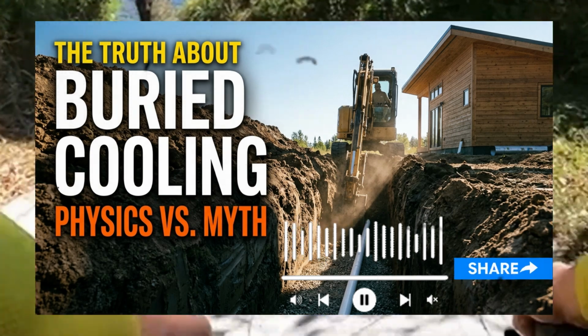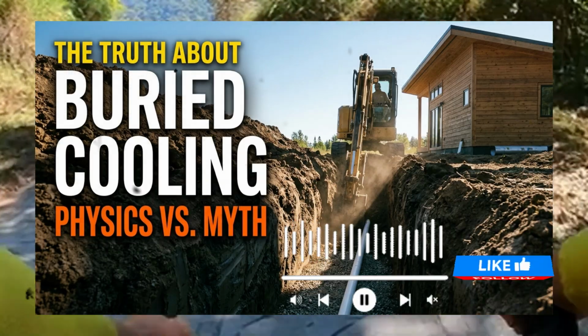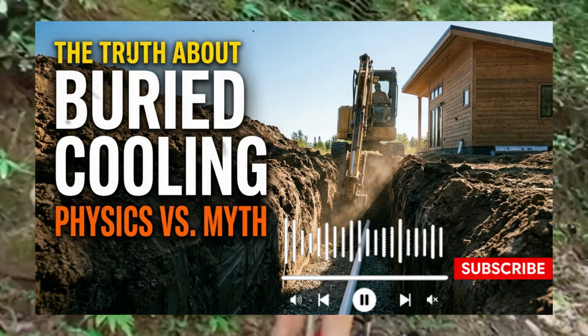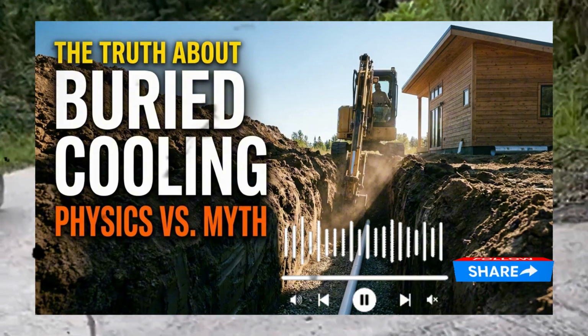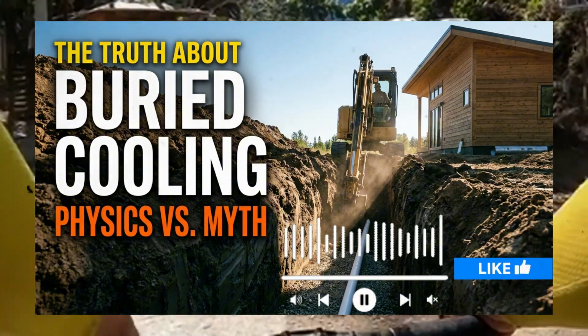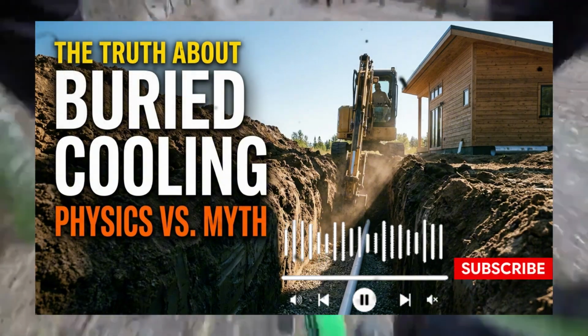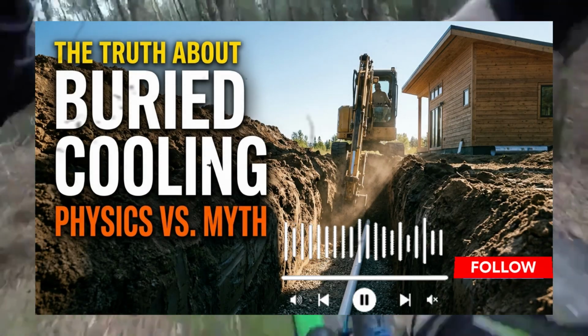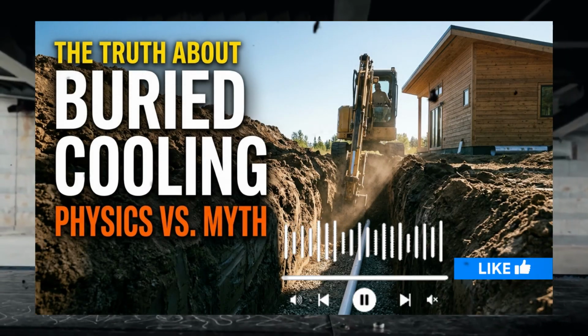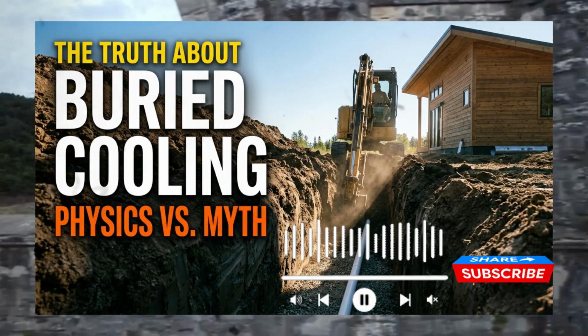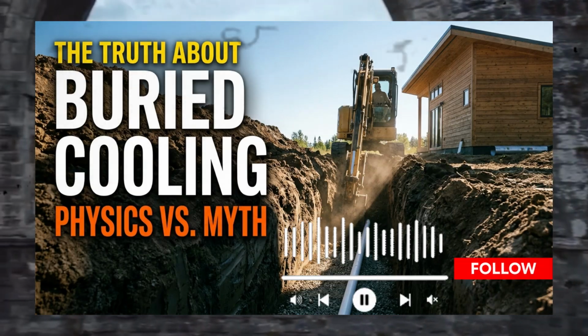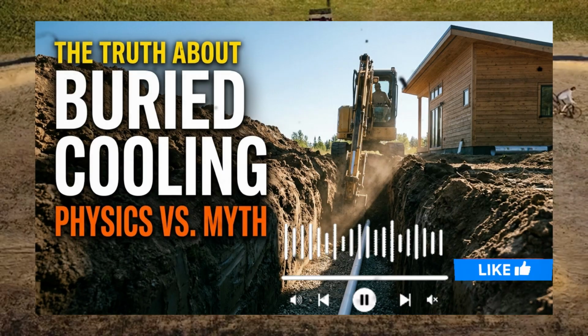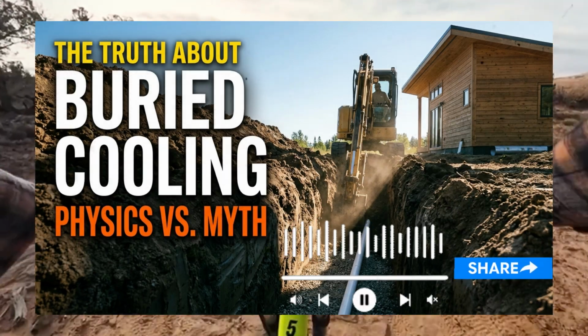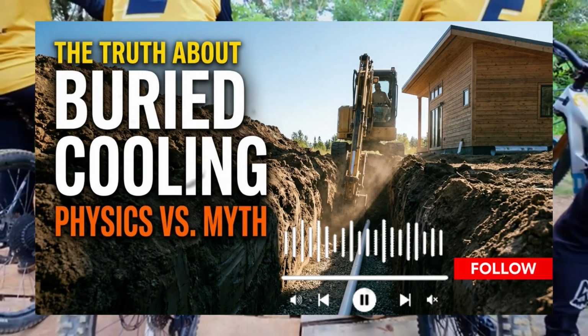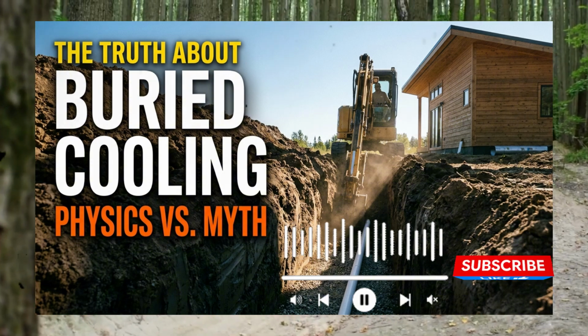This represented a massive thermal lift of 52 degrees, accomplished without a single watt of heating element power. Our home's primary heating system no longer had to fight to warm up freezing sub-zero air. It only had to raise the tempered 42-degree air up to 68 degrees, cutting our winter fuel consumption in half. But as the sub-zero temperatures persisted, we ran headfirst into a highly destructive physical trap: the ice plug phenomenon.